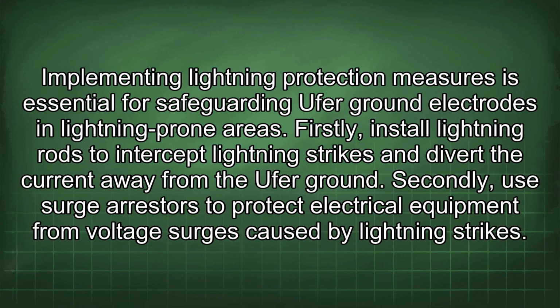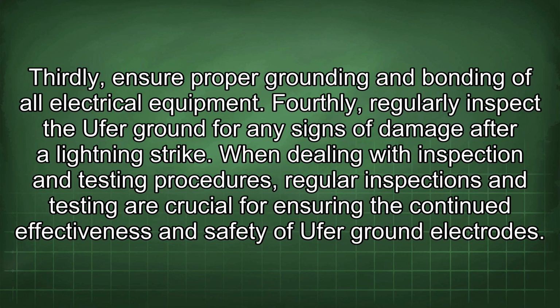Implementing lightning protection measures is essential for safeguarding Ufer ground electrodes in lightning-prone areas. Firstly, install lightning rods to intercept lightning strikes and divert the current away from the Ufer ground. Secondly, use surge arresters to protect electrical equipment from voltage surges caused by lightning strikes. Thirdly, ensure proper grounding and bonding of all electrical equipment. Fourthly, regularly inspect the Ufer ground for any signs of damage after a lightning strike.